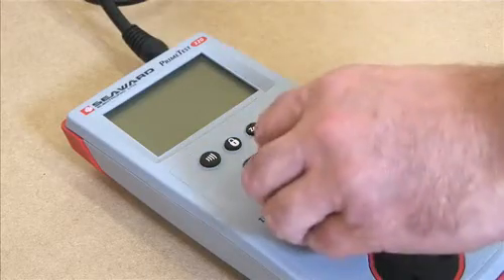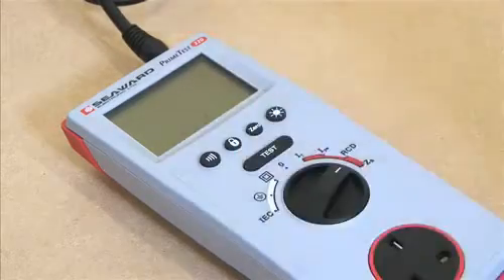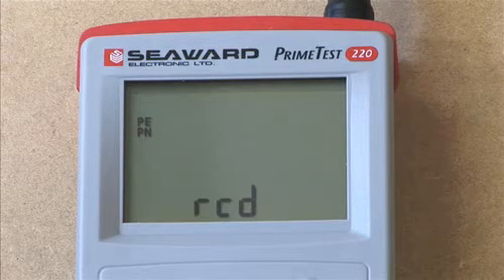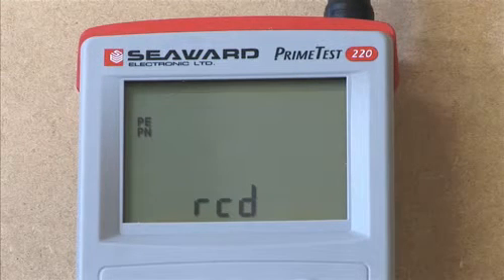Select RCD on the PrimeTest 220 rotary switch. The instrument will check the incoming mains supply for correct live neutral polarity and a valid earth connection.